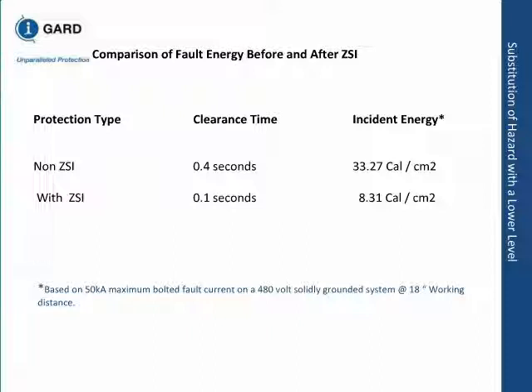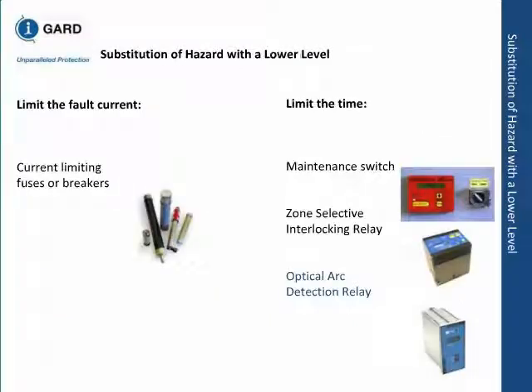Third is optical arc detection. When an arc flash happens, since the speed of light is the fastest, that is the first thing you see. That is the reason anybody exposed to arc flash, whether they are wearing protective clothing or not, will be momentarily blinded. Vision will come back, hopefully. So we use that property to cut down the clearing time. These are some of the sketches you can see when you have an arc flash optical relay.